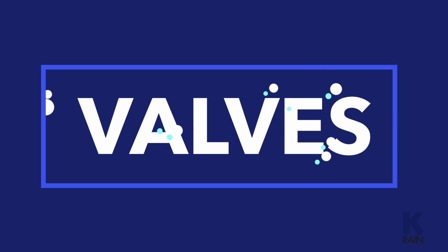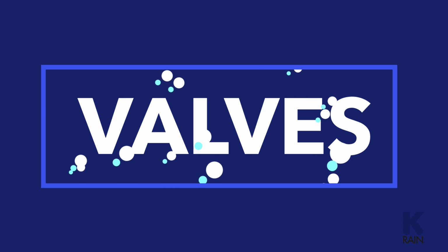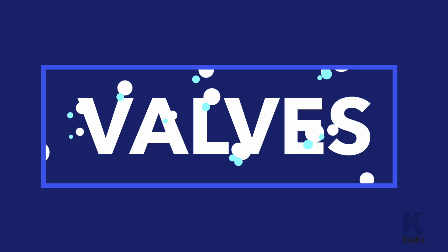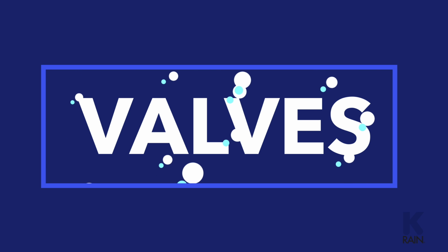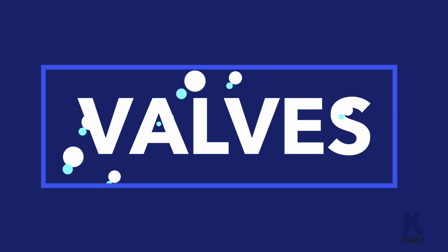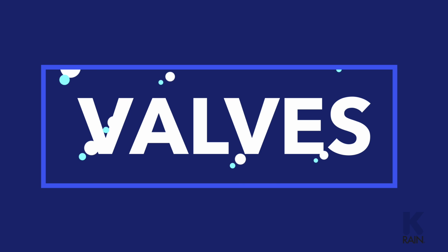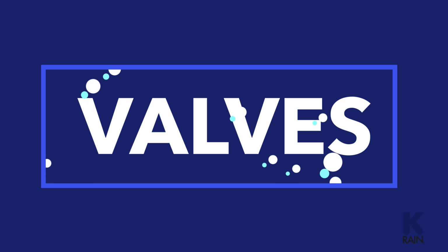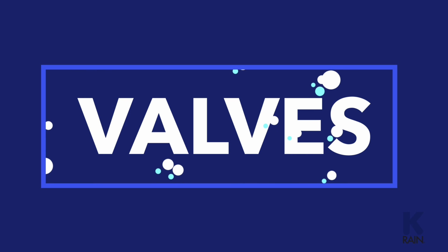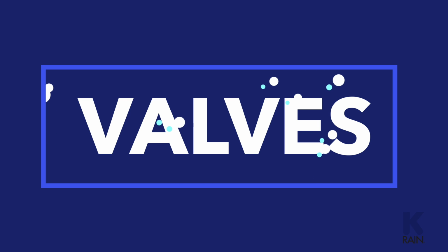Problems with valves usually present themselves when a particular zone either will not turn on or will not turn off. Diagnosing these problems correctly requires a working sense of how a valve works. So, we'll start with a review of the inner workings of the valve, and then go on to discuss reasons that valves either won't open or won't close.